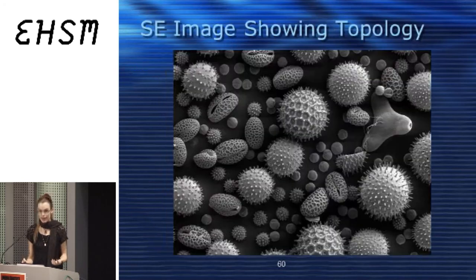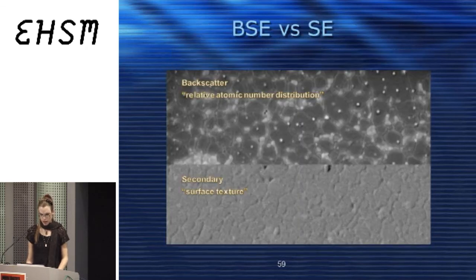That's really where you get pictures like this, which is not my picture, it's from Wikipedia, but you can tell that the spiky surfaces of these pollen grains show very brightly in secondary electron emissions, and the surfaces that are very flat and parallel to the beam don't show, they're very dark. There's a difference between backscatter and secondary. For backscatter, this is an image from Wikipedia. These dots are very high Z inclusions in the material that are somewhat deep, several microns deep, whereas at the bottom, you just see the surface texture.